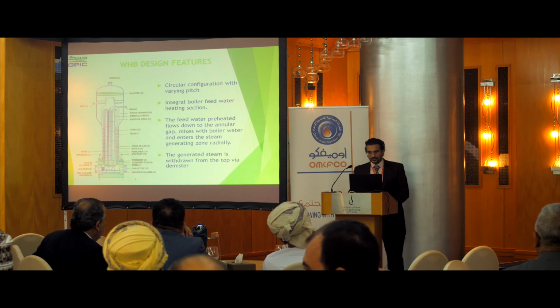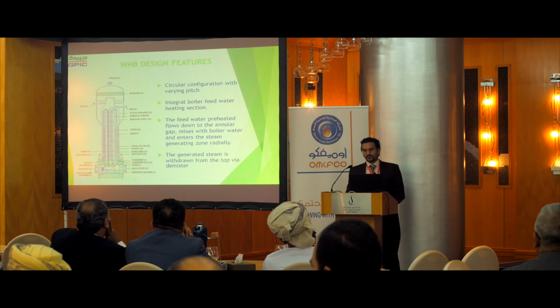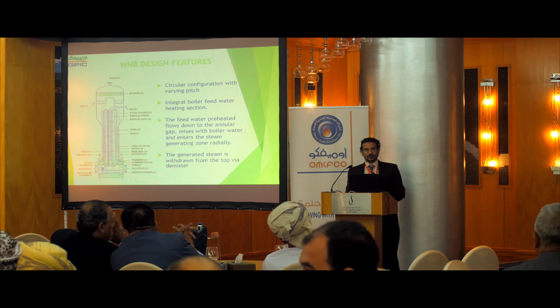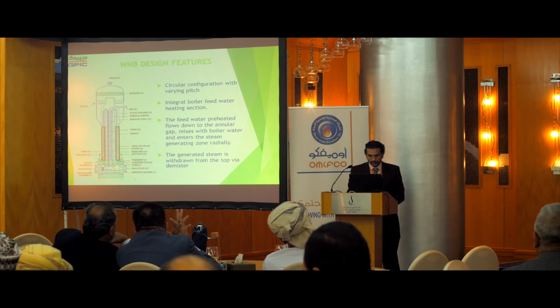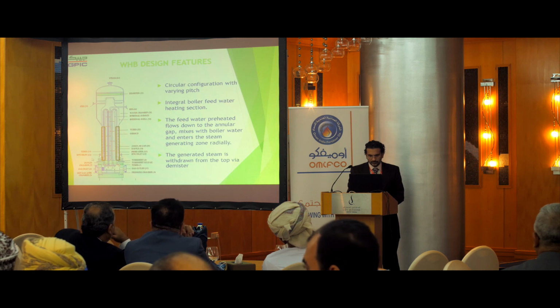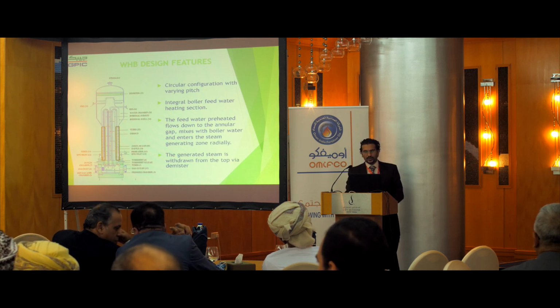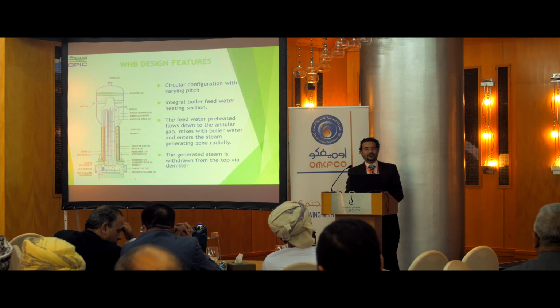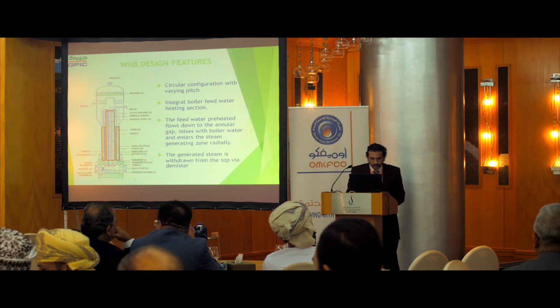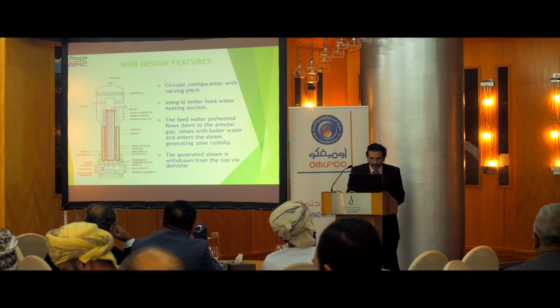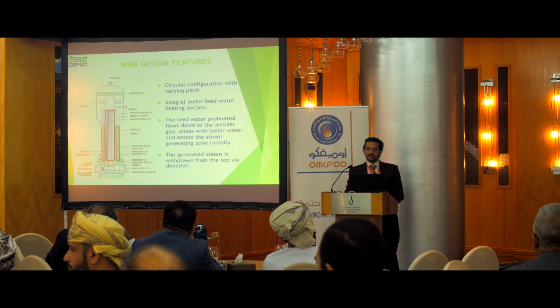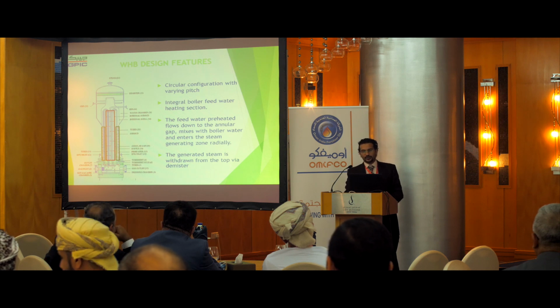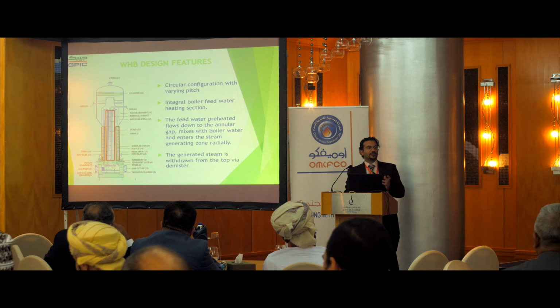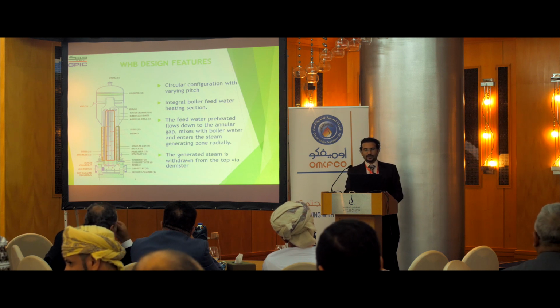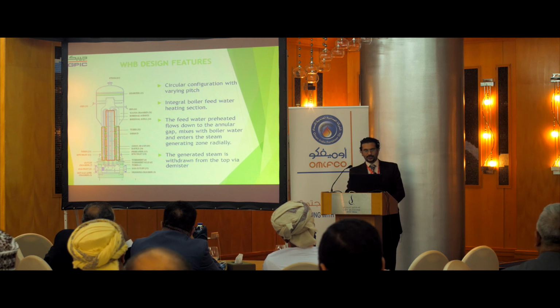This is the shell side circular configuration with varying pitch. The boiler feed water heating section is integral. The feed water enters on both sides of the waste heat boiler and flows down to the annular gap. It goes up, then flows down on the sides, entering the boiler generating zone, the boiler water zone, and generates saturated steam, which goes through a demister before leaving.